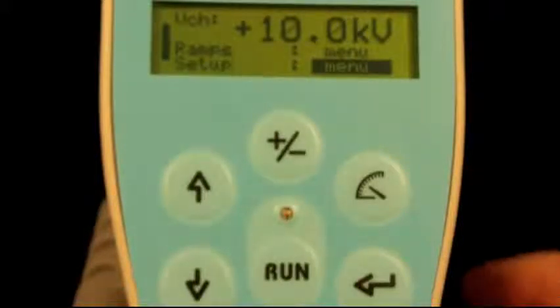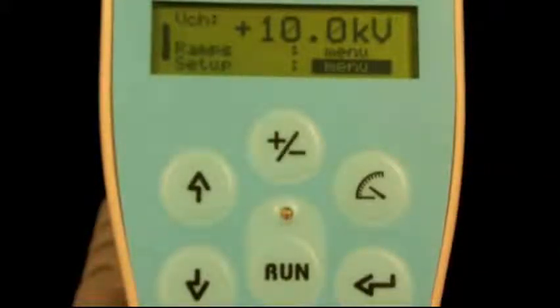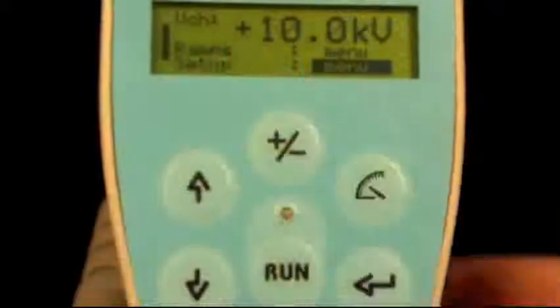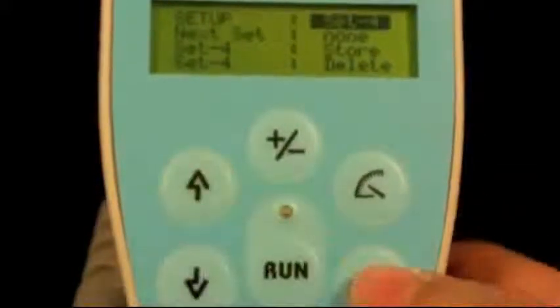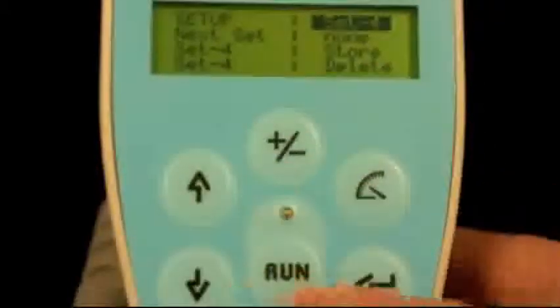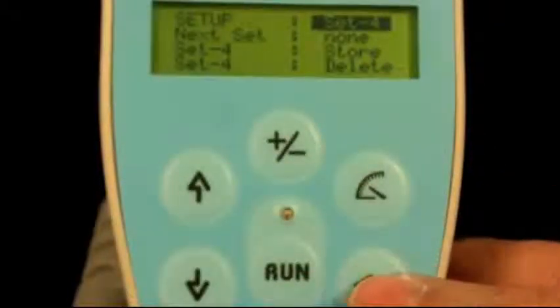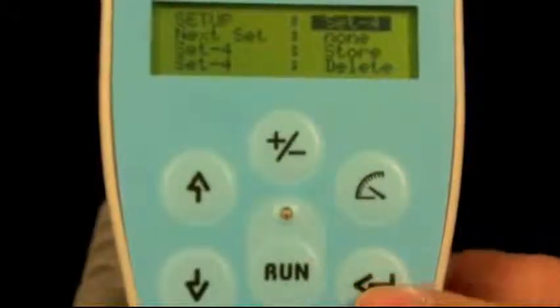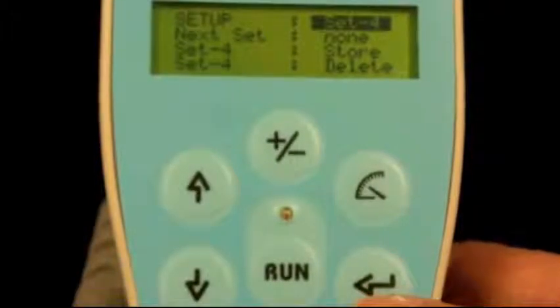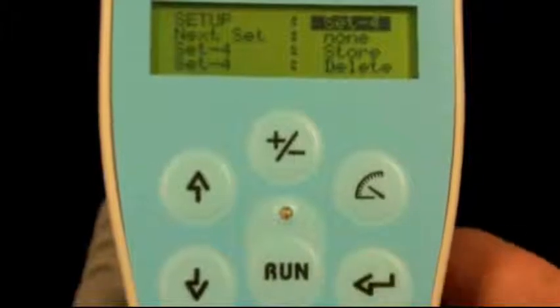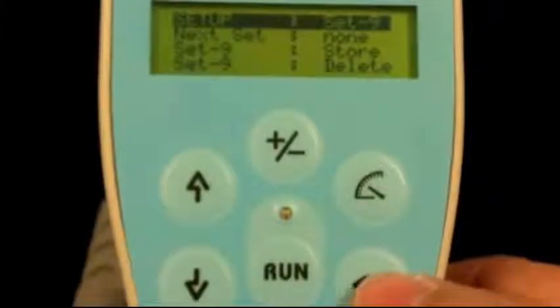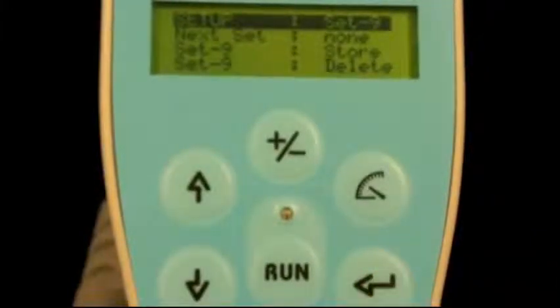The other option that the ESD3000 comes with are setups. You can select enter. The setups meaning it has capability of storing specific programs onto the ESD gun so you don't have to reprogram your gun every time. There are up to 9 locations available to store specific programs.